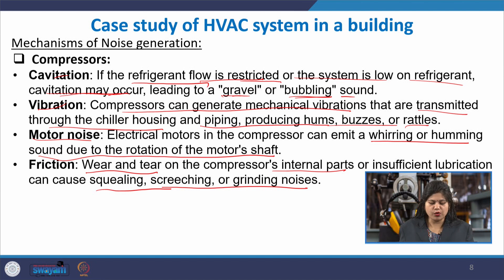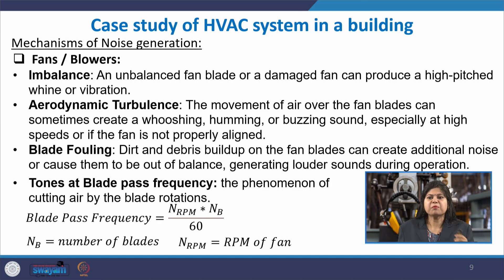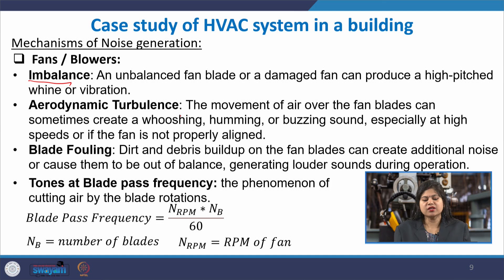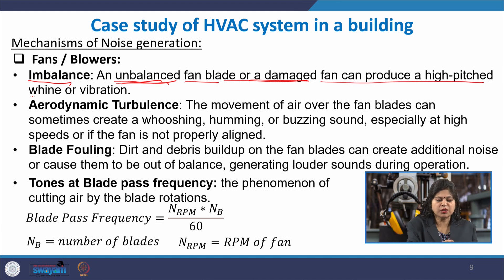Debris accumulation and worn-out parts with insufficient lubrication create sharp friction noise. For fans and blowers, typical mechanisms include airborne noise due to turbulence and blade pass frequency. Additional phenomena include imbalance from manufacturing defects or wear on the fan blade — as rotating machinery, imbalance produces a high-pitched vibration typically corresponding to the rotational frequency of the fan.